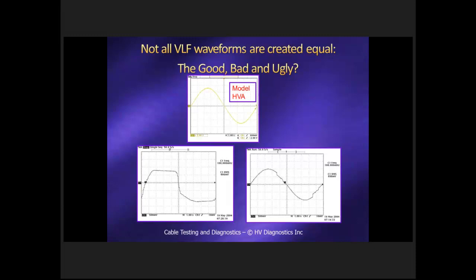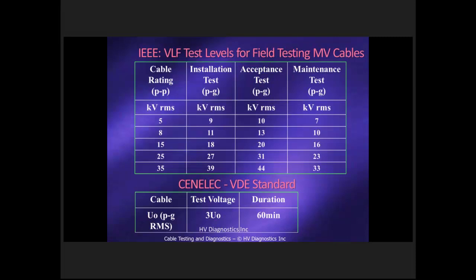If you look at the IEEE table, this is important because if you're going to be performing a partial discharge test offline, these will become your maximum voltages. So I'm not going to go through each voltage here, but you can see this is up from IEEE 400.2, I should say, for 15 kV cable, for example, common cable. If you're doing acceptance testing, you go up to 20 kV. If you're doing maintenance testing, you go up to 16 kV.